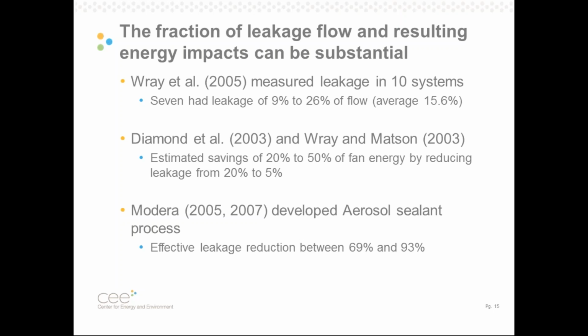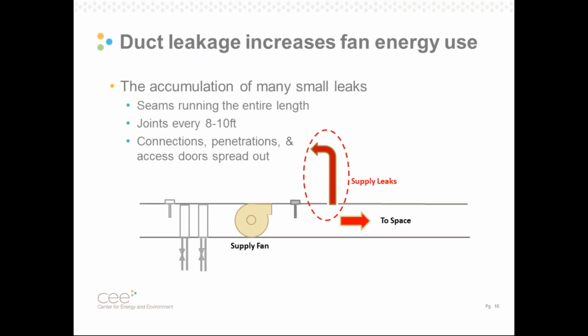And kind of one of the climaxes of that work out in California is that they developed a new process for sealing ductwork based on an aerosol system. And they showed very early on that it was highly effective for reducing duct leakage. They demonstrated 70 to 90% reductions in duct leakage on early tests. So let's dig into this a little bit more.